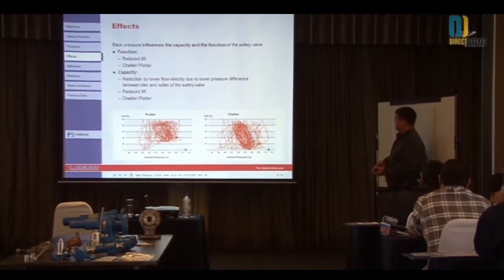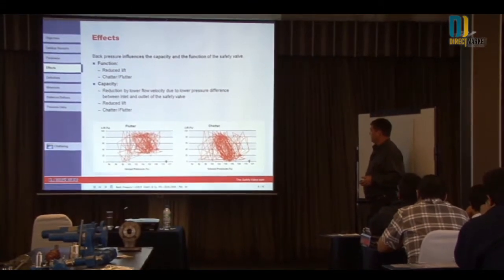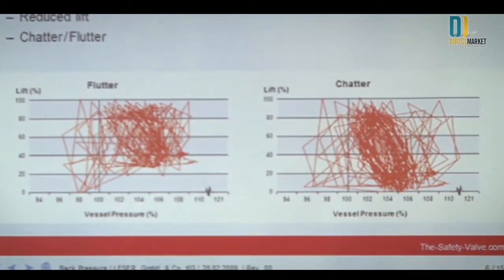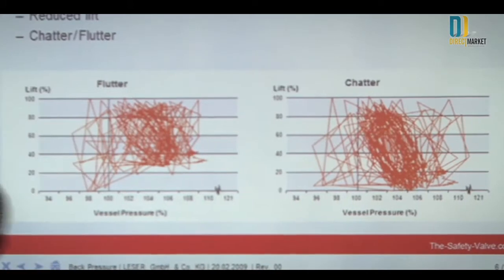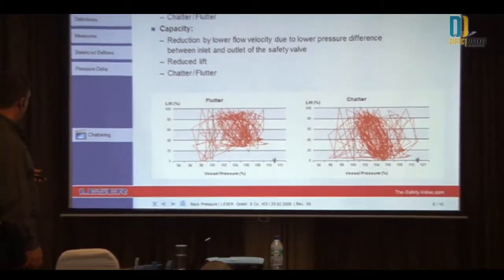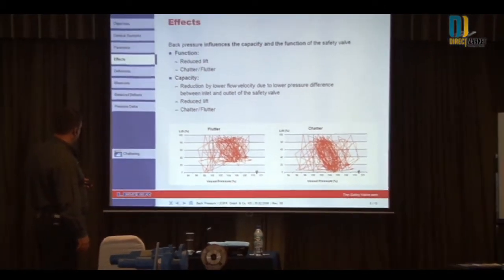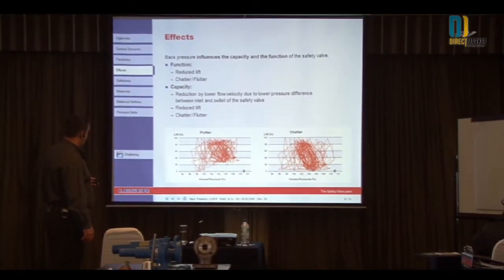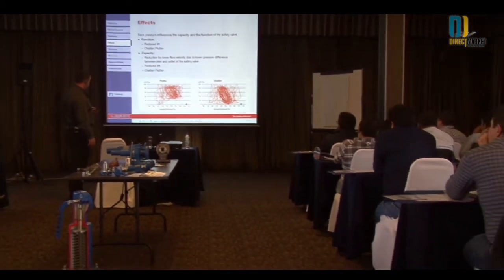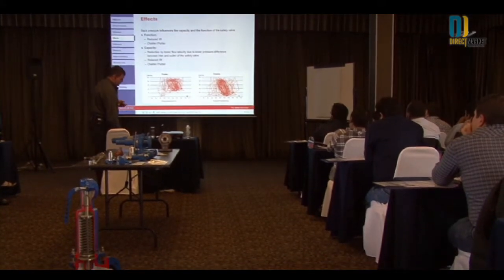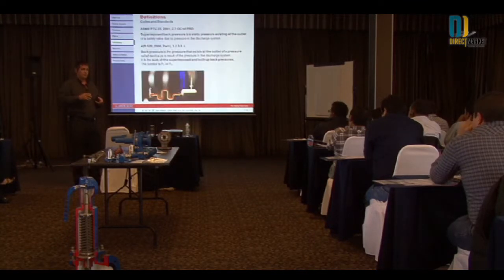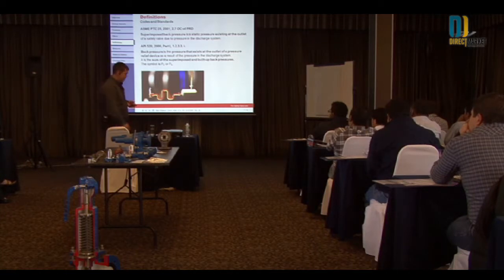Some of the characteristics influenced by back pressure: it would make the valve flutter or chatter, reducing the lift of the valve. It also reduces capacity through lower flow velocity due to a lower pressure difference between inlet and outlet of the safety valve. When the valve chatters and flutters, it will beat and ruin the components of the valve, requiring removal and maintenance.